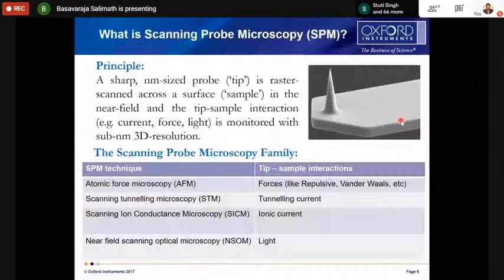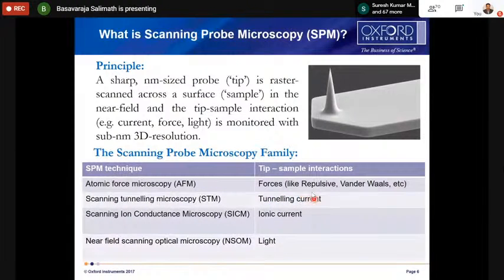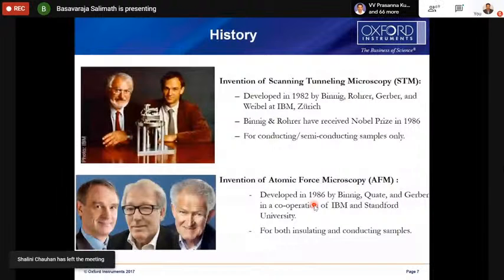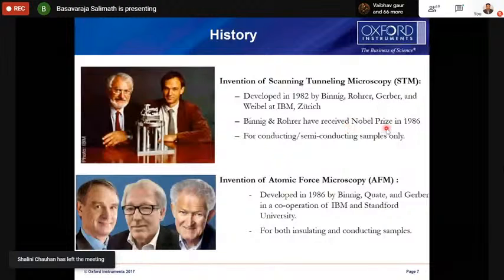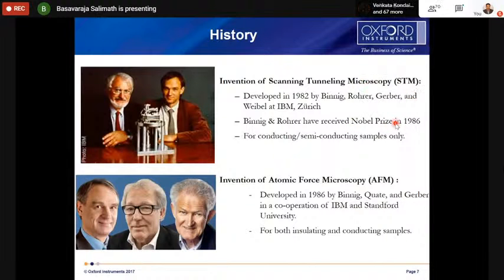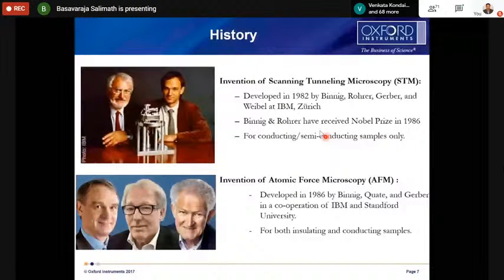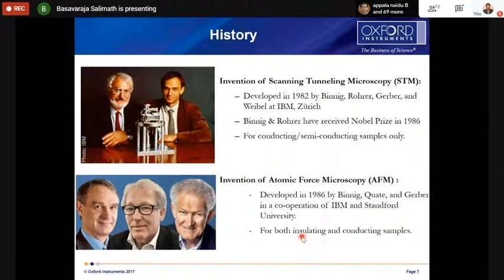As I mentioned in an earlier slide, the tip and sample interaction for STM is tunneling current. We get tunneling current only if the sample is a conducting or semiconducting sample. So you can't image insulating samples with STM, and that was the main drawback of STM. Later, in 1986, these people invented atomic force microscopy. Here the tip and sample interactions are forces, and those forces are there on all types of samples, whether conducting or insulating. So we can image all types of samples.